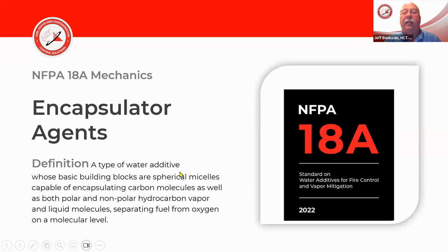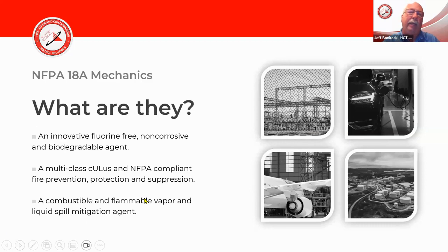We look at what and how this works. When we talk about powders and gels, inerting gases, foams, all the agents we're familiar with, then we get into NFPA 18A, we find we're talking about spherical micelles. That's the basic building block. Going deeper into the standard, there's section 7.7, the spherical micelle stability test, which tests the ability of these spherical micelles to encapsulate flammable or combustible liquids or vapors and hold them even in the presence of high heat.